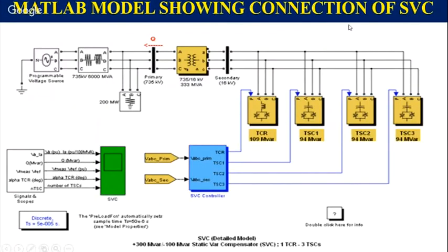This is the circuit. Here is the voltage source. This represents the transmission line. This is the load. This is the entire SVC, which is connected in parallel, in shunt, through this step down transformer. And this is the controller, which takes input only from the primary voltage and secondary voltage and gives pulses to the capacitor bank and firing angle to the thyristor controlled reactor.